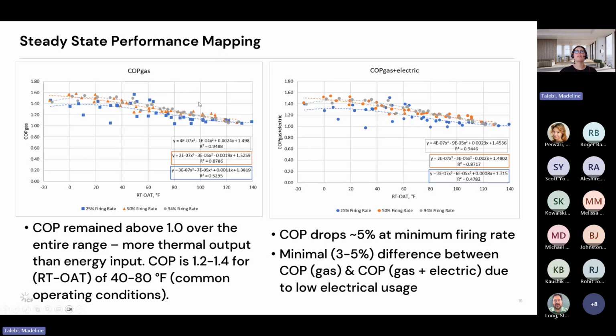And then looking at a comparison, the COP gas only, and on the right-hand side, the COP gas plus electric, and that kind of touches back on that power input curve I mentioned at the beginning where we saw a near constant. Taking a step back, you virtually see no difference between the COP gas only and the COP gas plus electric, but nonetheless I wanted to show this. We would expect this, again, according to that power input curve. Looking at the COP gas only curve, we see the COP remained above 1 over the entire range, and there's more thermal output than energy input. That's what it signifies when we see a COP above 1.